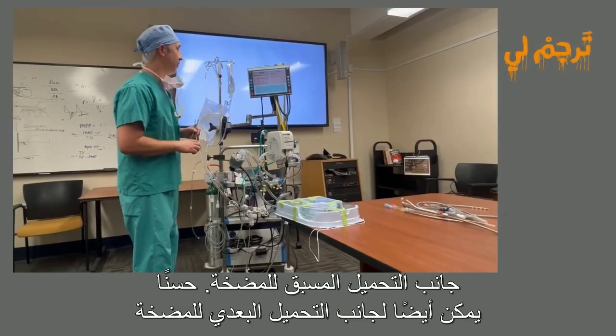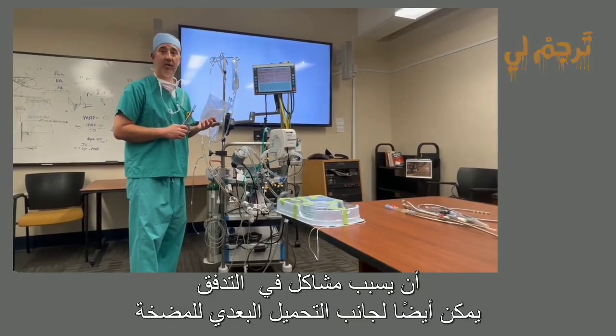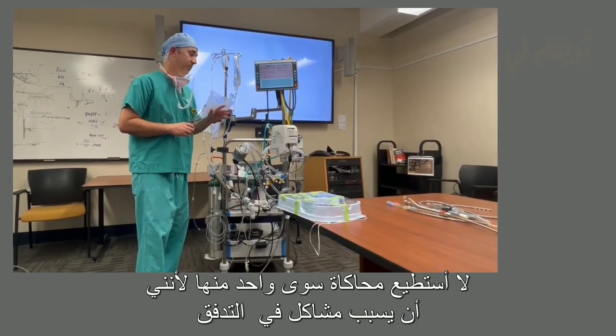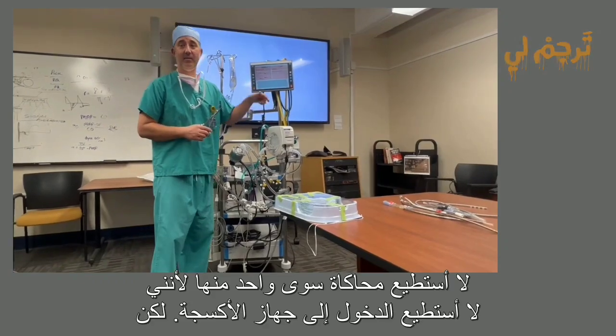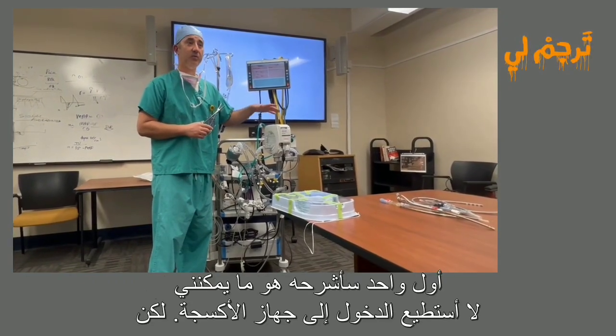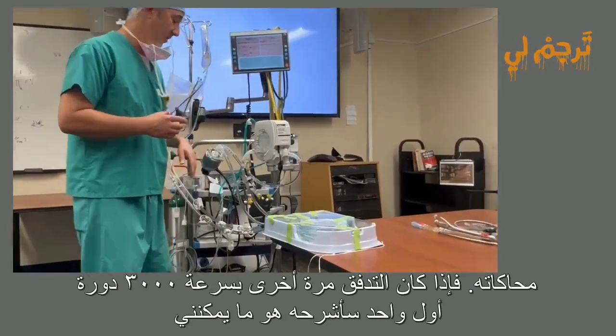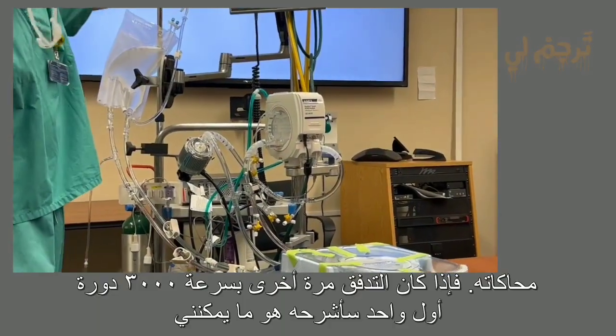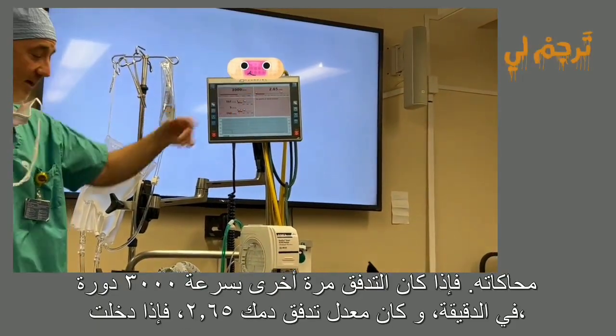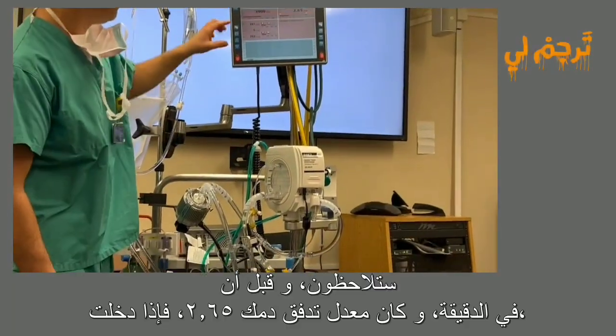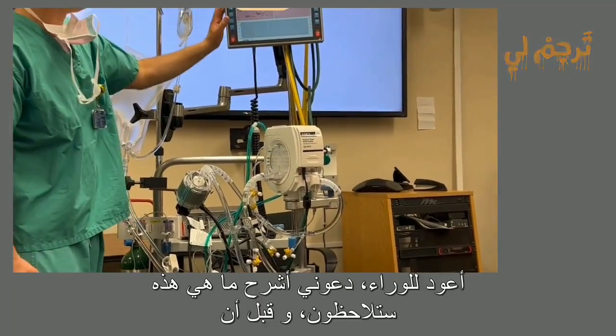The afterload side of the pump can also give you problems with flow. I can mimic only one of them because I can't get inside the oxygenator. But the first one I'll go over is what I can mimic. So if again you're flowing at 3,000 RPMs and your blood flow is 2.65, and before that, let me back up, let me go over what these pressures are.